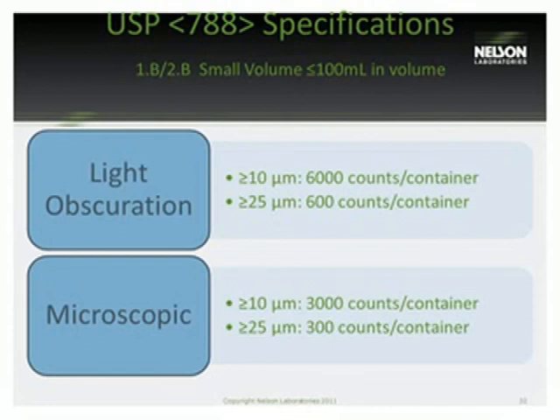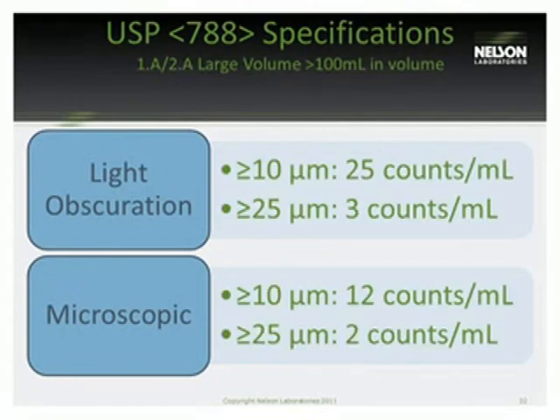It is typically recommended to test a larger particle size with devices, like the FDA recommended greater than or equal to 50 microns. These are the specifications for large volume. Those previous specifications were for small volume. Small volume are more frequently adopted to devices because it gives it as counts per container. Large volume gives it as counts per mil.